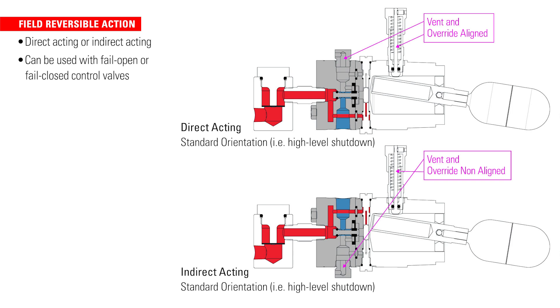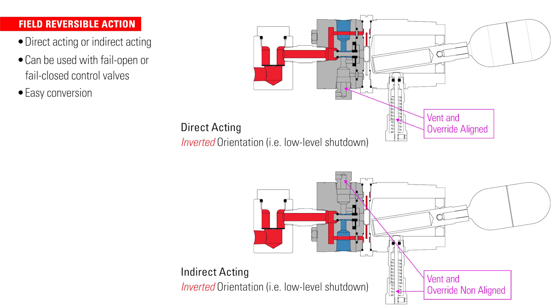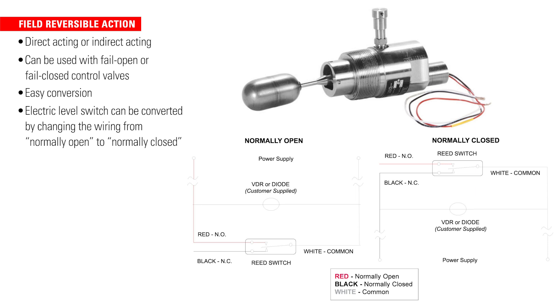The level switch is field reversible from direct acting to indirect acting, so it can be used in conjunction with a fail-open or a fail-closed control valve. You can easily convert the pneumatic switch from direct to indirect by rotating the pilot body 180 degrees. The electric level switch can also be converted by changing the wiring from normally open to normally closed, or vice versa.